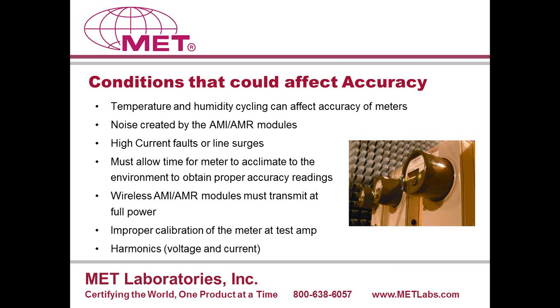So in general, some of the conditions that we see that would affect accuracy, here I would say that there are two sets of tests, if you will. There's a group of accuracy related tests. Essentially, when you look at the standard, tests number 1 through 14 are really the core of the accuracy tests out of the standard. Tests 15 through 38 are really external influences, environmental influences, radiated immunity influences. These are different influences that the product is going to see out in the field. They could affect accuracy. So based on that, we have temperature and humidity cycling that's performed in the standard. There's an ambient temperature test where you're looking at accuracy at unity power factor and 0.5 lagging power factor. That'll run from ambient temperature up to 50 degrees C and down to minus 20 degrees C.